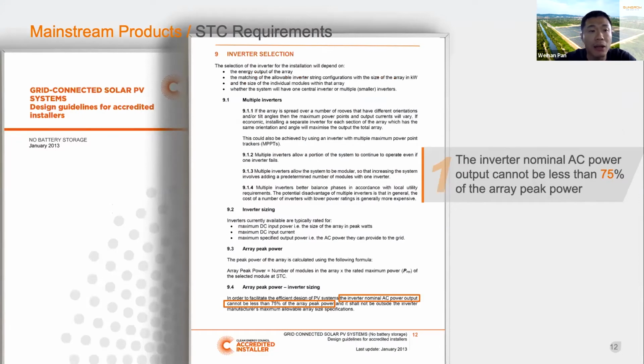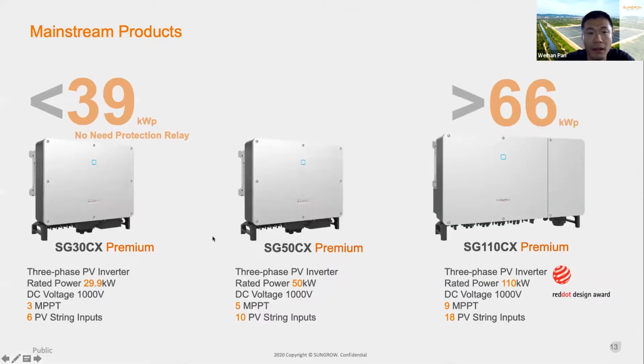And the other one that you could find on the grid connection solar PV system design guideline, also published by CEC, mentioned that the AC part of the power, which means the inverter nominal AC power, cannot be less than 75% of the array peak power. For example, if you install 100 kilowatt DC from PV panel, then your minimum inverter nominal power will be 75 kilowatt. And that's why for this year, we announced 3 C&I inverters.